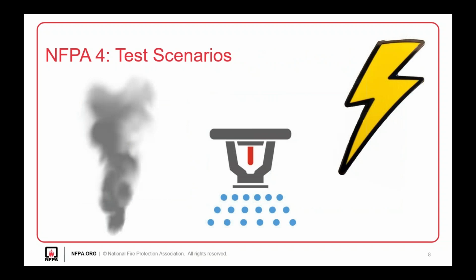When we look at test scenarios, again, NFPA 4 being so scalable, we're not going to say if you have this type of system or building, this is the exact test scenario you need. What's important to note is that NFPA 4 requires one or a combination of the presence of smoke, water flow from a sprinkler, or loss of normal power to conduct an integrated system test. The presence of smoke is a scenario that could initiate smoke detectors, elevator recall, door closures, and smoke control systems.